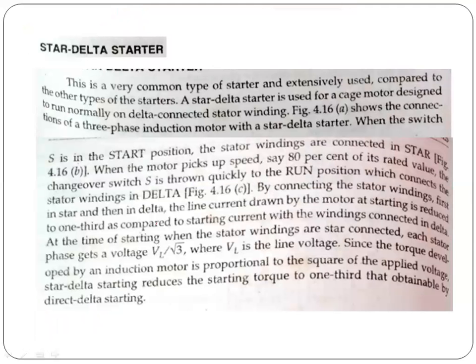So now let us discuss what is written here. S is the start point, the stator windings are connected in star. When the motor picks up the speed, say about 80% of the rated value, a changeover switch S is thrown quickly to the run position, which connects the stator winding in delta. By connecting the stator winding first in star and then in delta, the line current drawn by the motor at starting is reduced to one-third as compared to the starting current with the windings connected in delta.